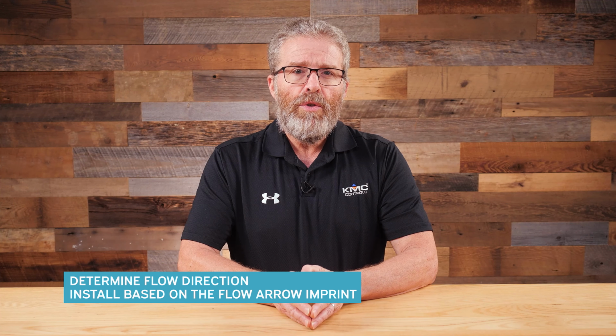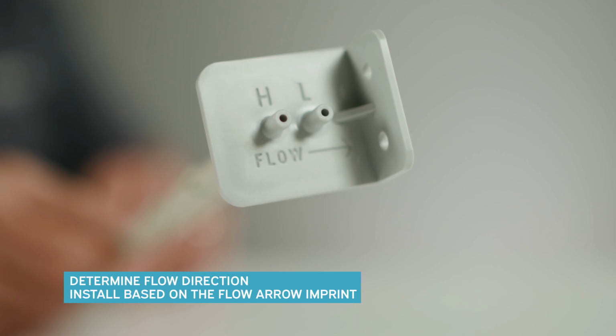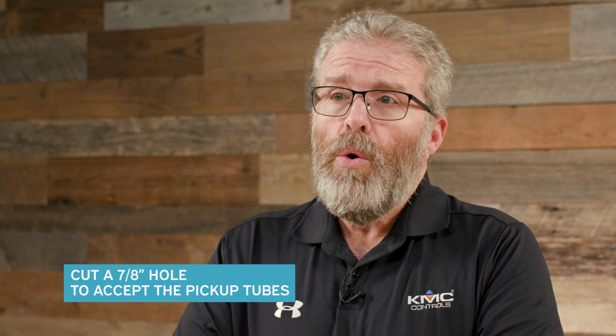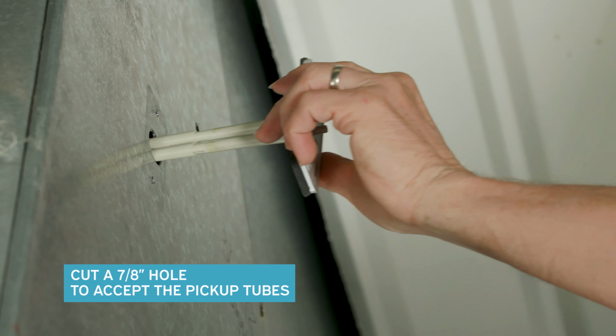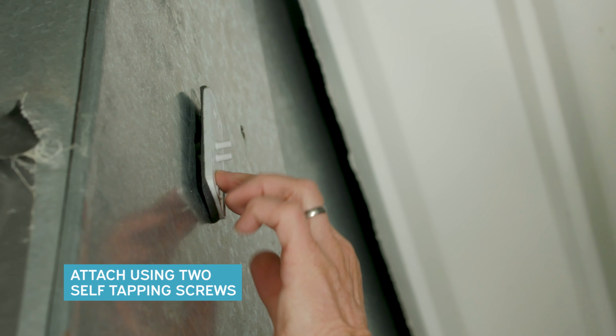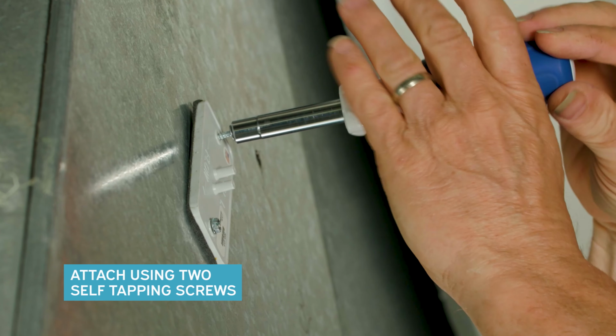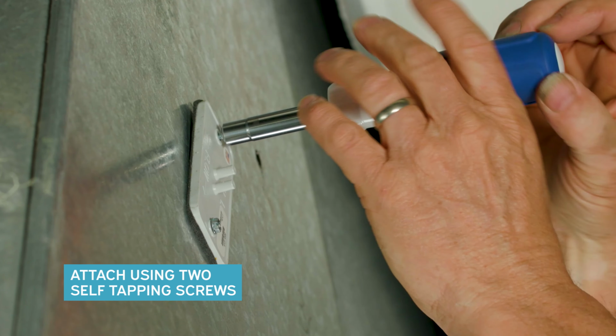The first step for installing the air pressure pickup tubes in the supply air duct using the SSS 1000 is to determine the duct's flow direction and install the pickup tubes based on the flow arrow imprint. Note, the pickup tubes must be mounted with the arrow pointing in the direction of the airflow. Next, cut a 7/8 inch hole in the duct to accept the pickup tubes. Finally, attach the pickup tubes to the duct using 2 self-tapping screws inserted through the 3/16 inch mounting holes. Repeat these steps to mount the remaining pickup tubes.